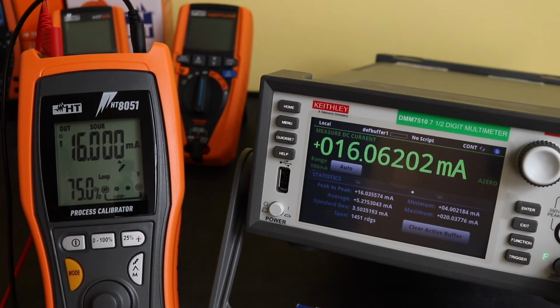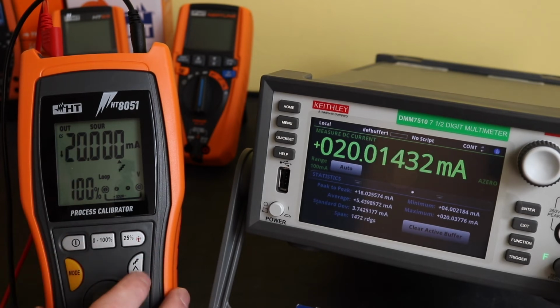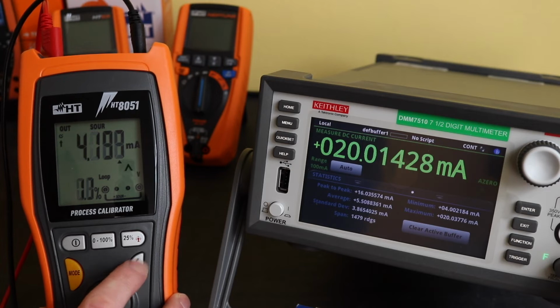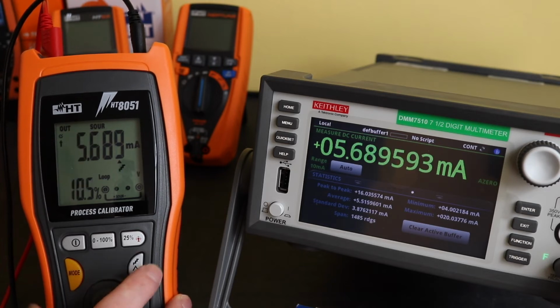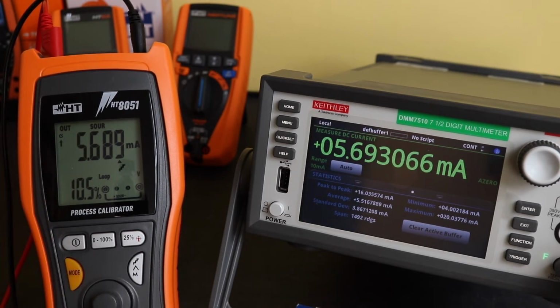And so now on the 50, on 75, up to 100, and then it'll start going back down again. But if I change it to another ramp and then go back to the step one again, it's just sheer luck where it actually ends up. That first ramp function seems a little bit untidy to me, as opposed to the other two.